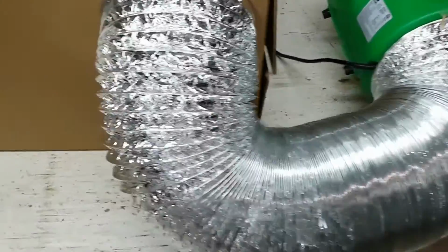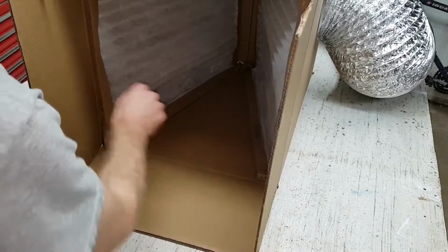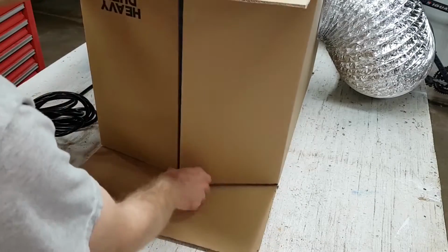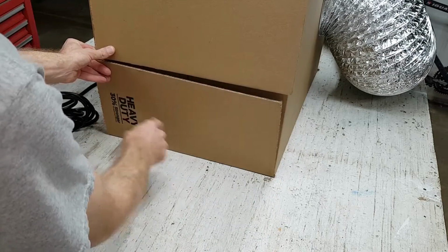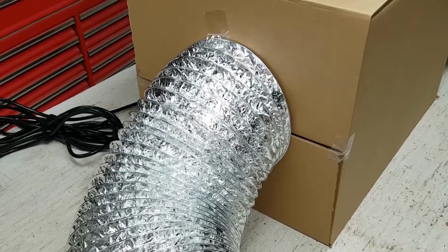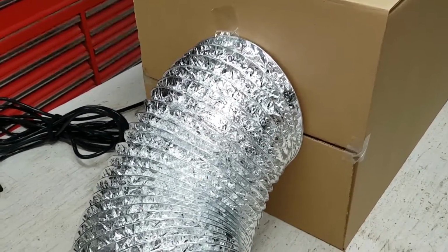Each blower inlet gets a filter of its own with this configuration, but they can be set up to share filters. I don't know if it matters either way. The inlet for the filter box would be cut in the end here. And I think a 10-inch foil duct from the inlet to the ductwork in the house would be enough, but 12 inches would probably be more appropriate.